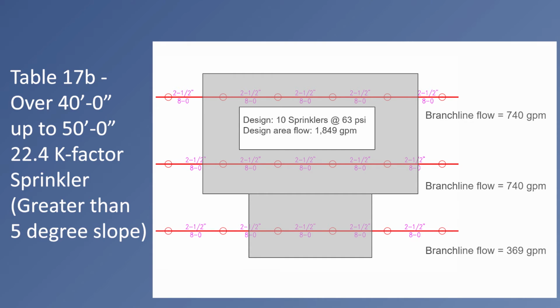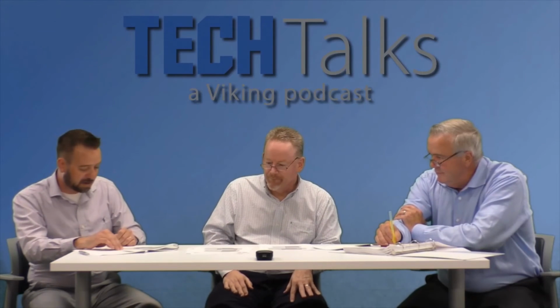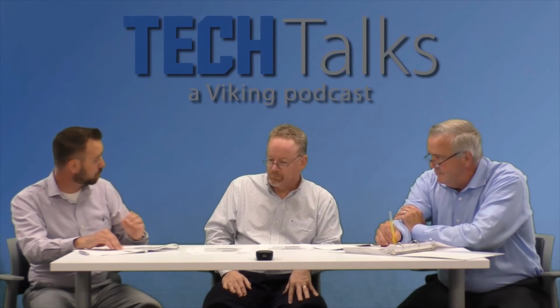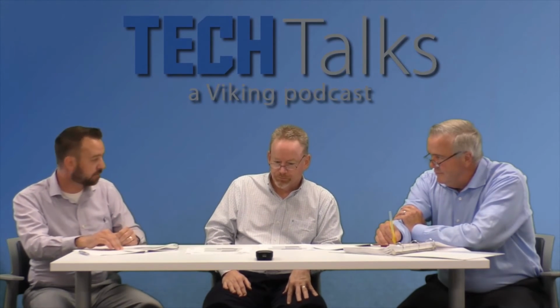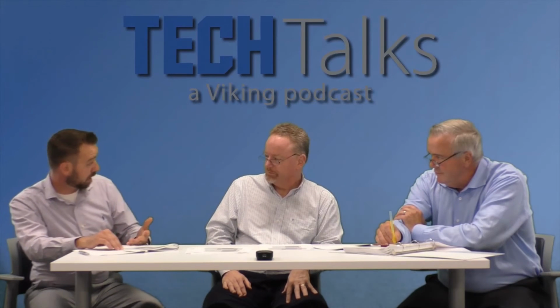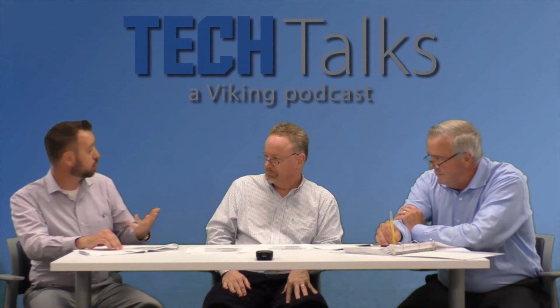So in this case, our overall flow increased to 1849, which doesn't seem like that much more than the less than 5-degree slope, which was just a little less than that. But once we go to the branch line flow, now we're looking at 740 gallons per minute because we added the extra sprinkler on those two most remote branch lines, as compared to 537 GPM when we look at the K28 sprinkler.